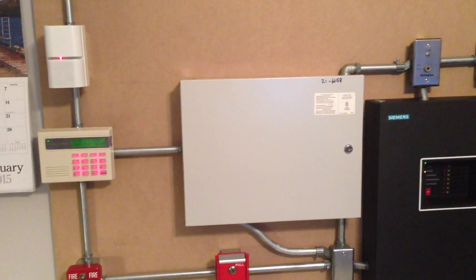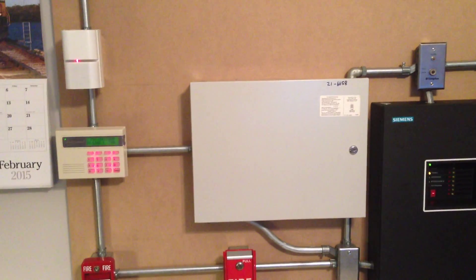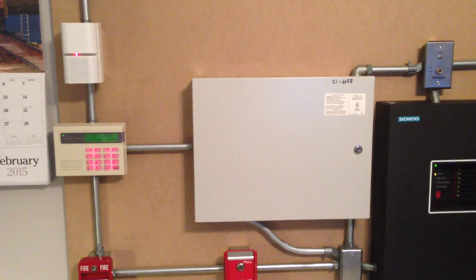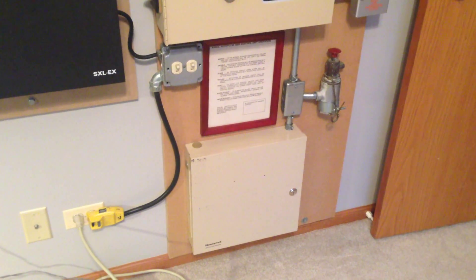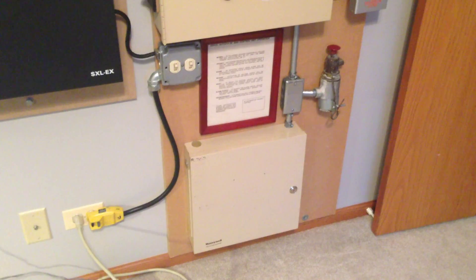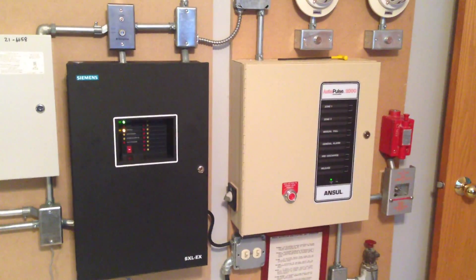This was removed from a building that I'm really familiar with, and it's sadly being torn down. A lot of the stuff on this panel I'm actually already familiar with from when it was installed. For example, this box down here is filled with Radionics Pop-It modules that used to monitor some of the equipment that was in that building. I've maintained those zones for the history, as well as added new ones to monitor the fire equipment.